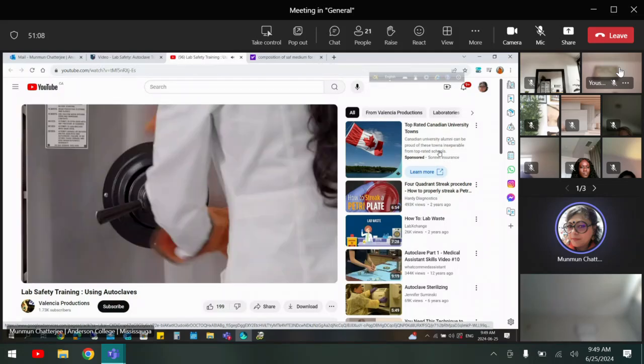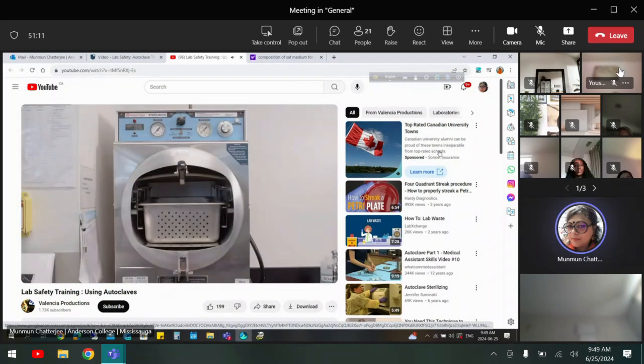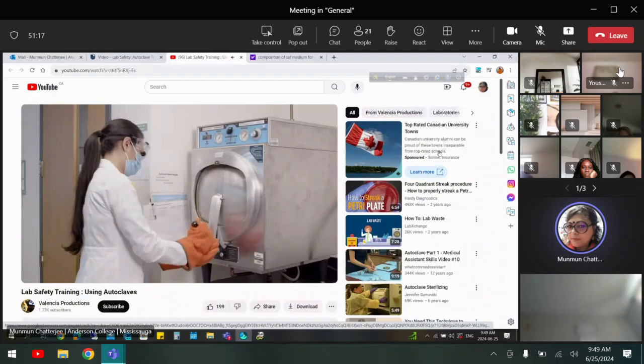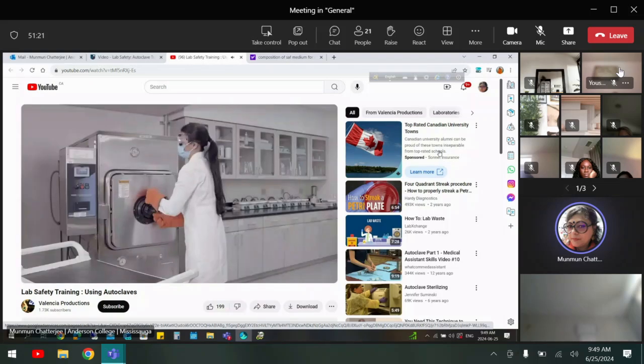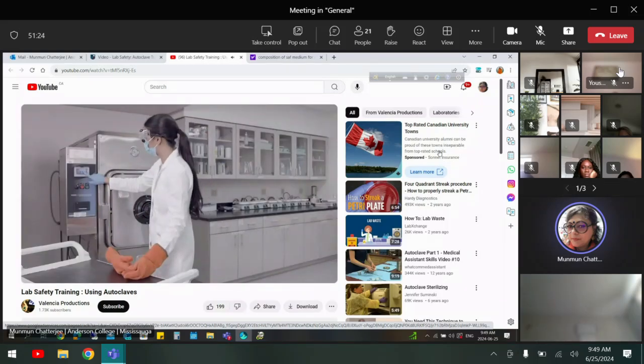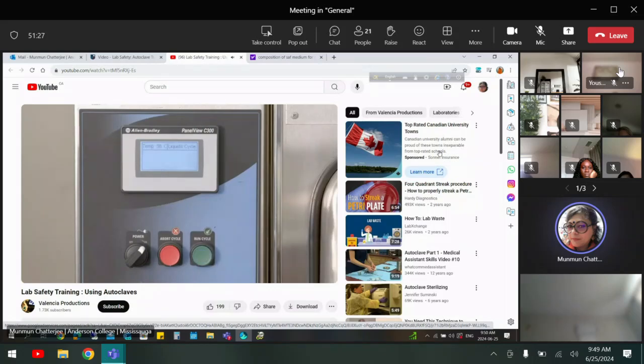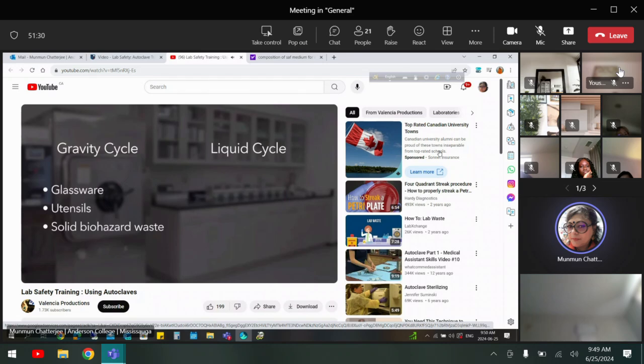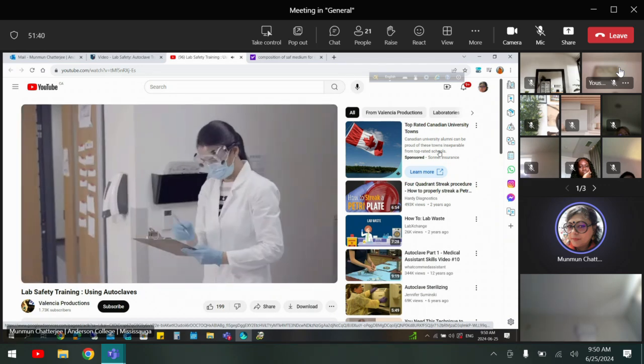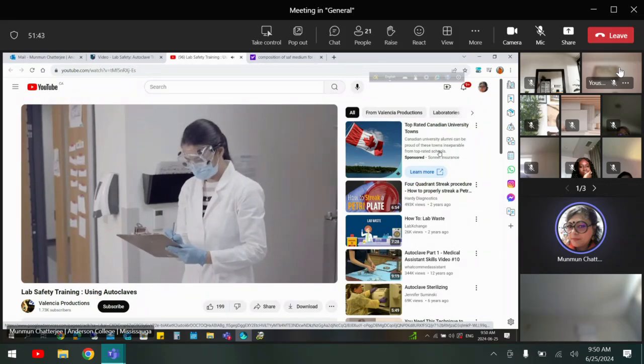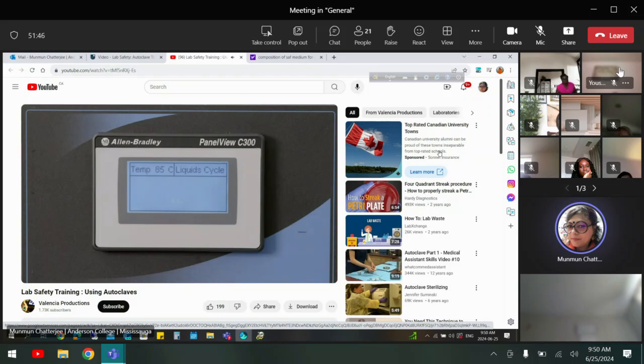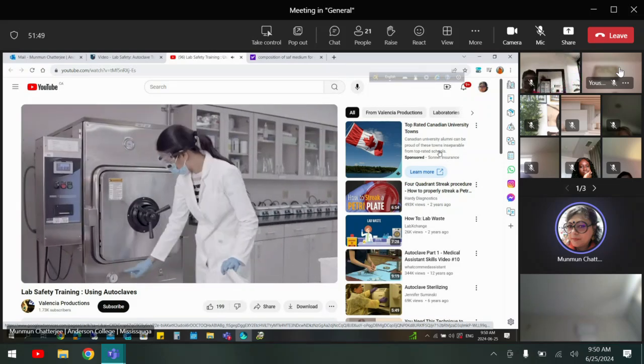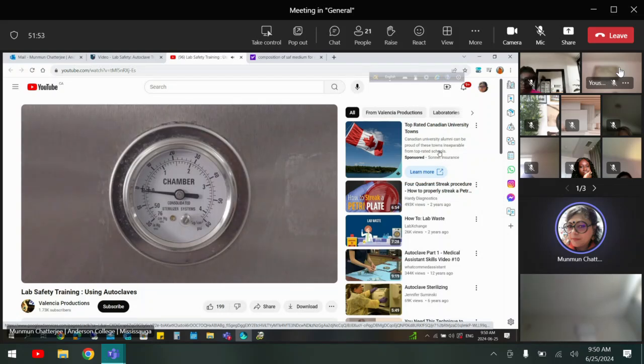After loading the autoclave, close and lock the autoclave. At Valencia, the model of your autoclave may vary based on your campus, and therefore you may encounter different door lock mechanisms. Select the appropriate cycle. If you are unsure, check with your lab supervisor or your manufacturer's manual. Typically, the gravity cycle is used for glassware, utensils, and biohazard waste. The liquid cycle is used for liquids as it has a slower exhaust to prevent boil over. Once you start the cycle, make sure to log the cycle information in the lab's autoclave log. Before opening the door at the end of the cycle, first check to ensure the temperature on the gauge has dropped to a safe range and the chamber pressure is at 0 psi.